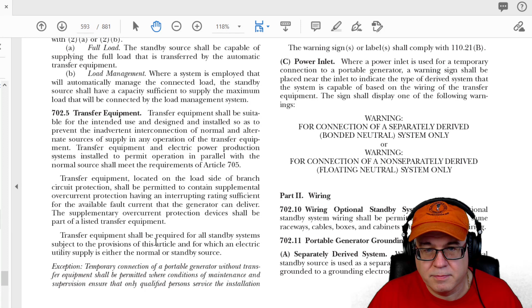And we do have an answer, just so everybody knows. So the question is - let's look at it real quick - transfer equipment, optional standby. Obviously the answer has to be in the transfer equipment section, it has to be, right? So what am I looking for here? It says transfer equipment shall be suitable for the intended use and designed, installed so as to prevent the inadvertent interconnection, that looks very familiar, of normal and alternate source.